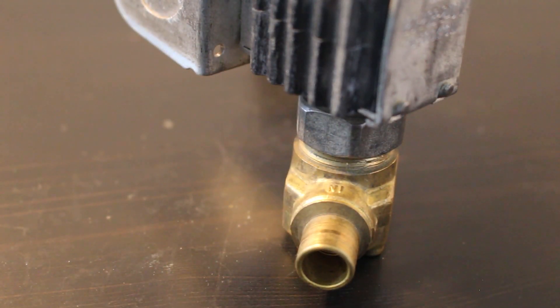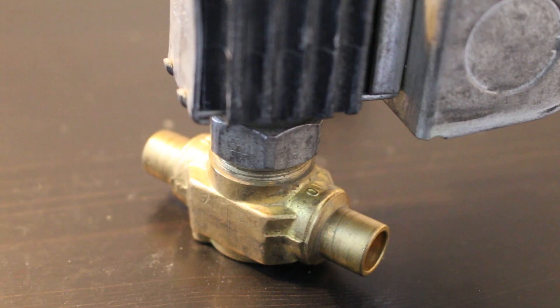The inlet is connected to the side of the system with the highest pressure. In this way, the pressure of the system is used to help keep the valve closed. If the valve is reversed and installed the opposite way, the pressure of the system could be enough to overcome the tension of the spring and lift the plunger off of the seat. This would cause the valve to leak.